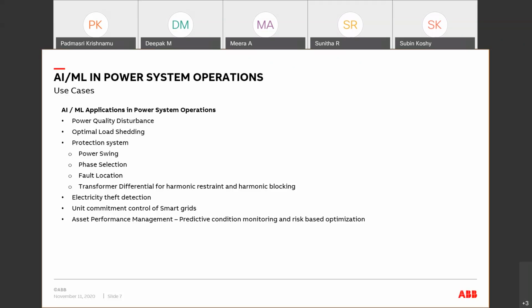Basically, you could use many methods. Use of artificial neural networks or random forest to effectively identify the inrush. So basically, in a transformer, what is the main thing that we are constantly looking at? We want to differentiate an internal fault from an inrush situation or overexcitation situation. Under both the conditions, we would not want the relay to trip, but only during an internal short circuit fault, we would expect the relay to trip.